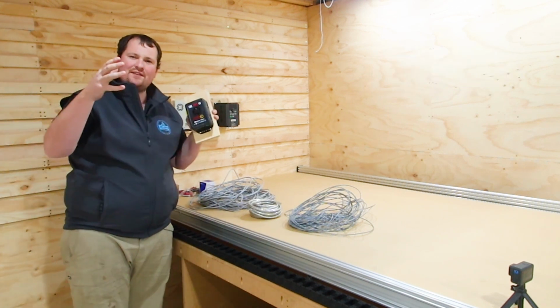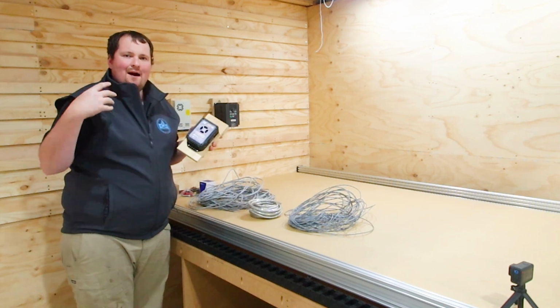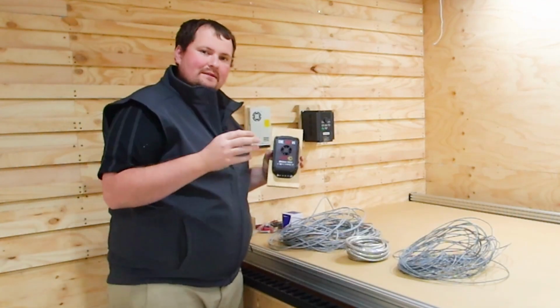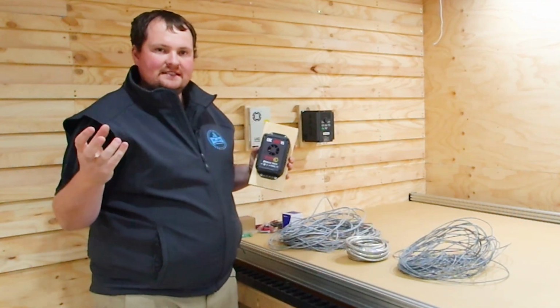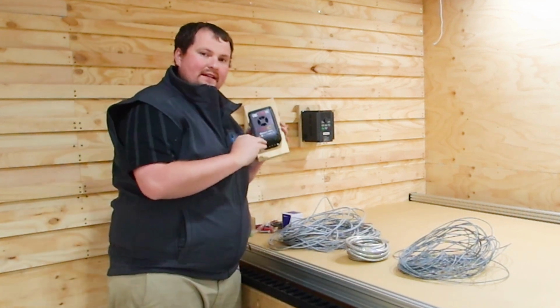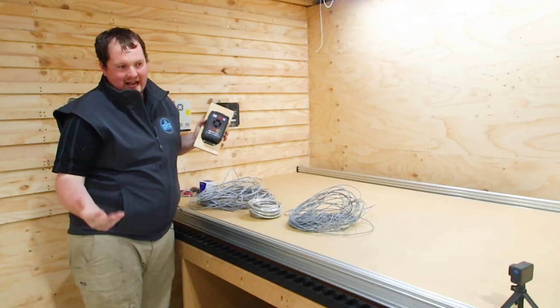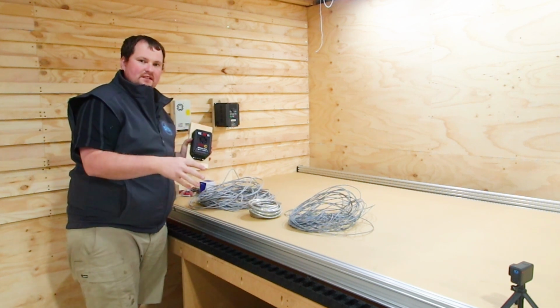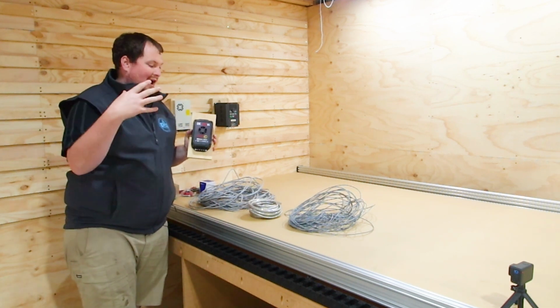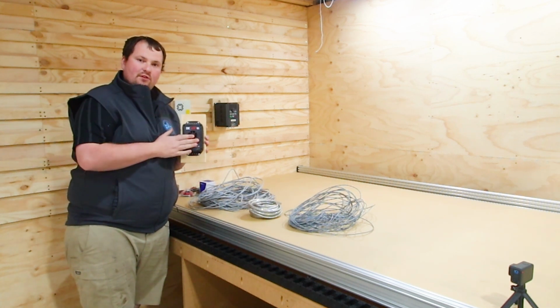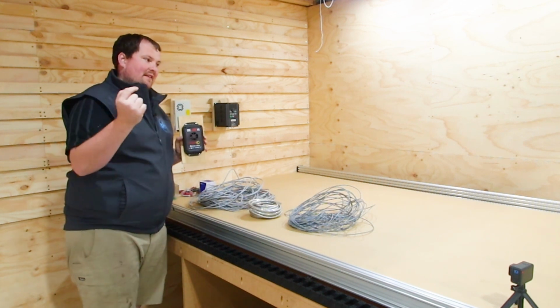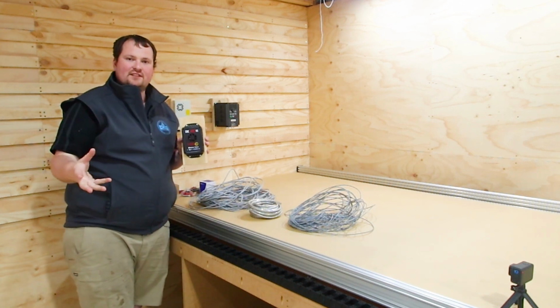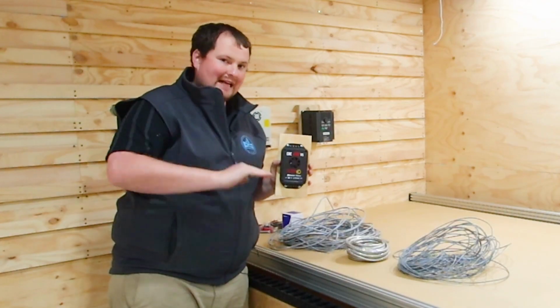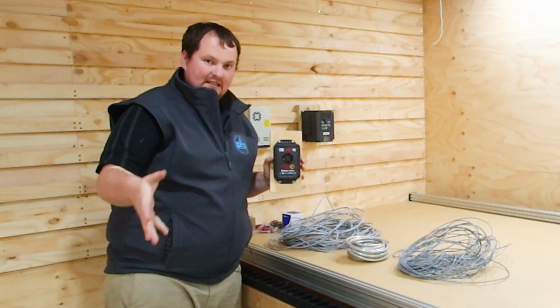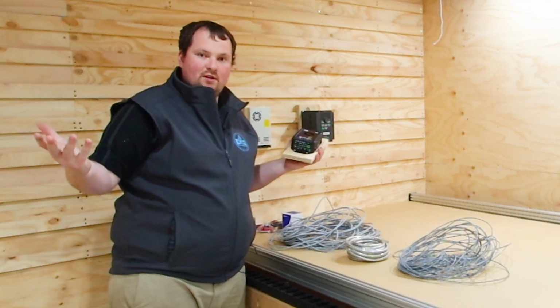It can run your emergency stop, however that will only pause the machine, and my thought process is: if it's an emergency, I want to kill the power. If it's just a 'hey, I need to stop the machine and pause it', I'll use the software. So I won't run my emergency stop through my controller—I'll run that through my power supply and get an electrician to wire that up so it cuts the power to the machine because it's an emergency. That's my thought pattern; you're welcome to do whichever you please.